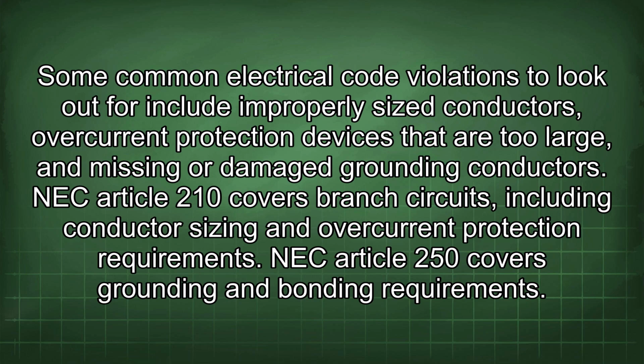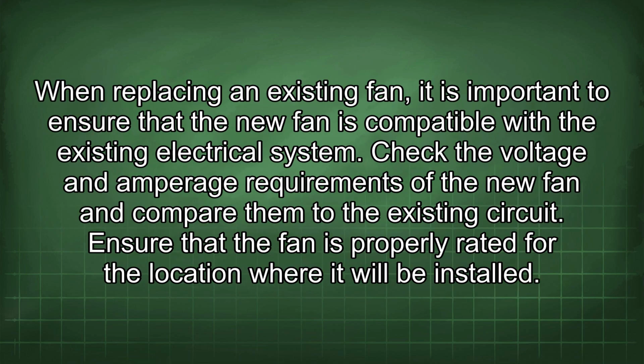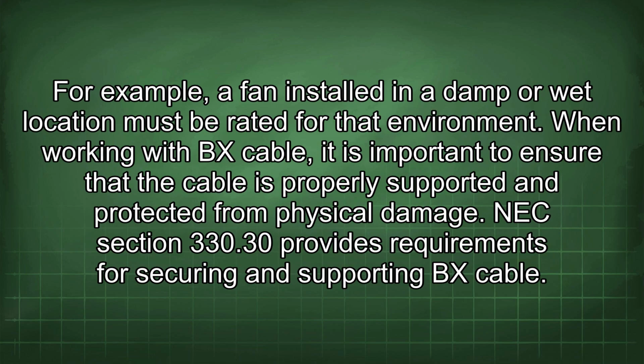NEC Article 210 covers branch circuits, including conductor sizing and overcurrent protection requirements. NEC Article 250 covers grounding and bonding requirements. When replacing an existing fan, it is important to ensure that the new fan is compatible with the existing electrical system. Check the voltage and amperage requirements of the new fan and compare them to the existing circuit. Ensure that the fan is properly rated for the location where it will be installed. For example, a fan installed in a damp or wet location must be rated for that environment.